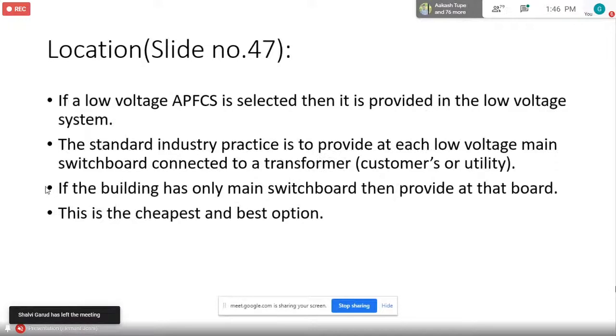If low voltage APFC is selected, then it is provided in the low voltage system. The standard industry practice is to provide it at each low voltage main switchboard connected to a transformer. So every transformer is connected to a main low voltage switchboard, and you provide the system in that switchboard. If the building has only one main switchboard, then you need to provide it only at that one main board. If it has more than one transformer, suppose it has 4 transformers, then you have to provide the system at each of the 4 main switchboards. This is the cheapest and best option. Don't waste time on any other option.